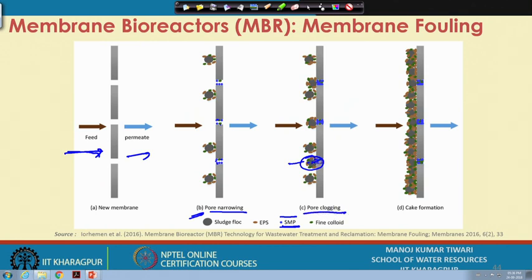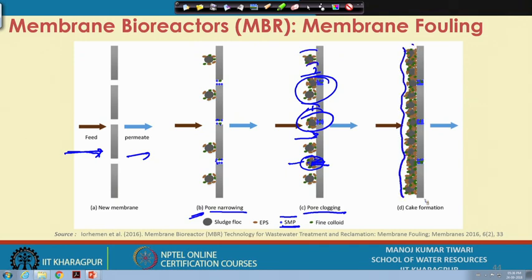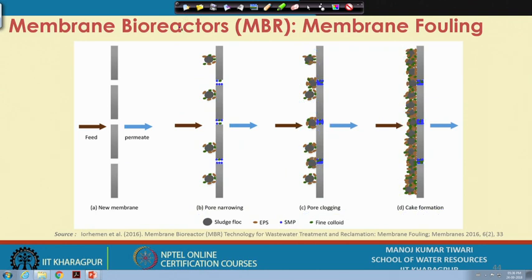After pore narrowing, materials diffuse inside the pores, leading to pore clogging. Eventually, if not removed, things stick on the surface since there is no passage through the clogged pores — slowly a cake forms on the membrane surface, which is called cake formation. At this stage, the flow through the membrane is completely stopped and one cannot obtain the desired treatment or retention from the membrane system.